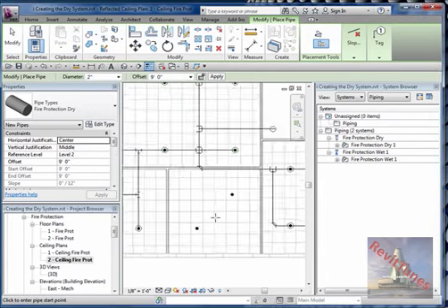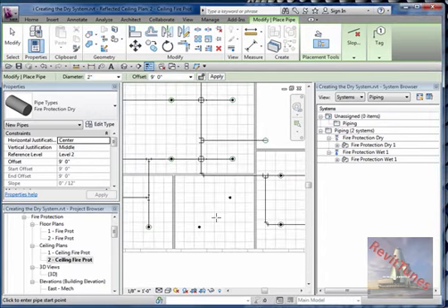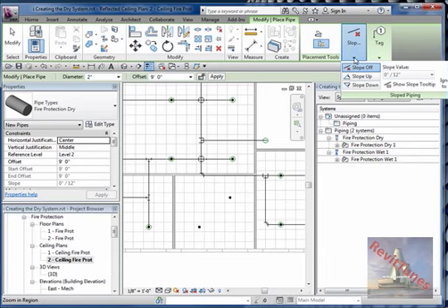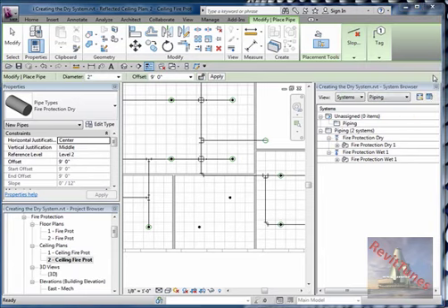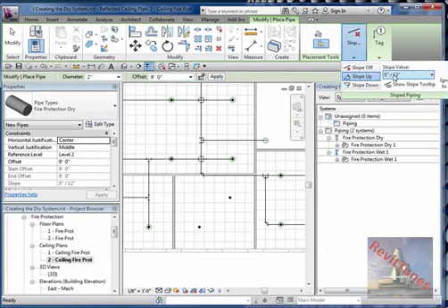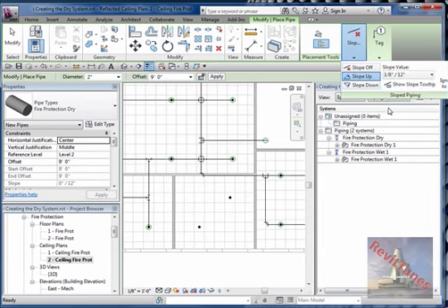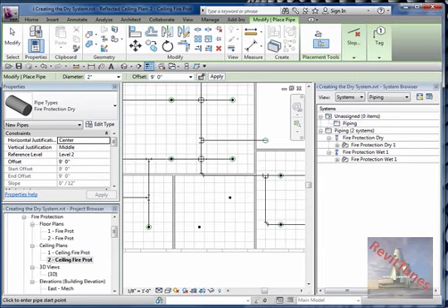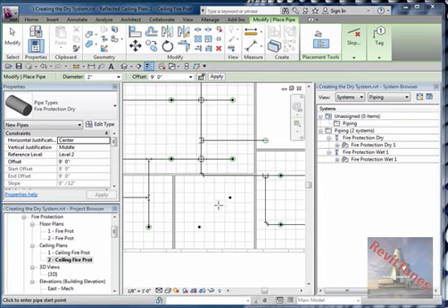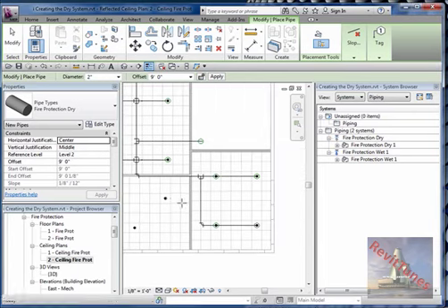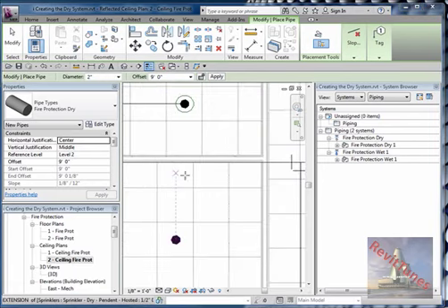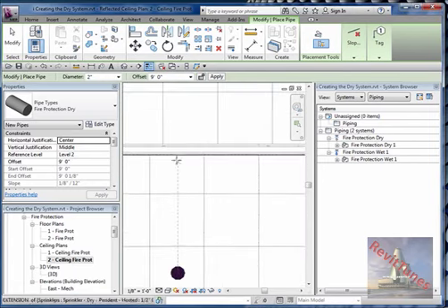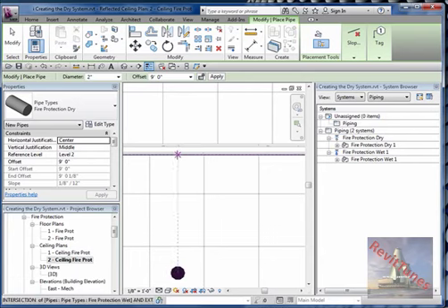By default we have diameter two and nine foot offset from the floor. Remember we did some settings before. This button which is automatic connect needs to be on. The other one is justification. I'm not going to click around on that one right now. Because we want this pipe to be always dry it needs a slope. So let's choose a slope. Depending on what direction you are going to draw it, so I'm going to draw it from the connector, slope up. We are going to put one eighth of an inch in one foot.